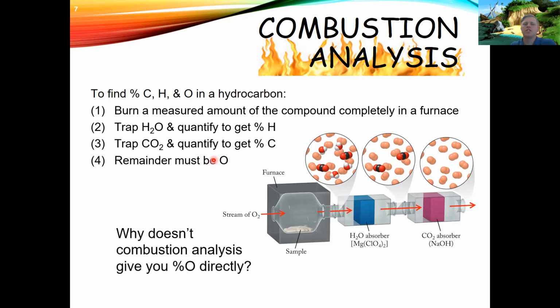Now, why doesn't combustion analysis give you the percent oxygen directly like it does for hydrogen and carbon? Well, the reason is because we're pumping oxygen in here, we're reacting the hydrogen with oxygen, we're reacting the carbon with oxygen, so we're actually kind of flooding this whole system with oxygen.